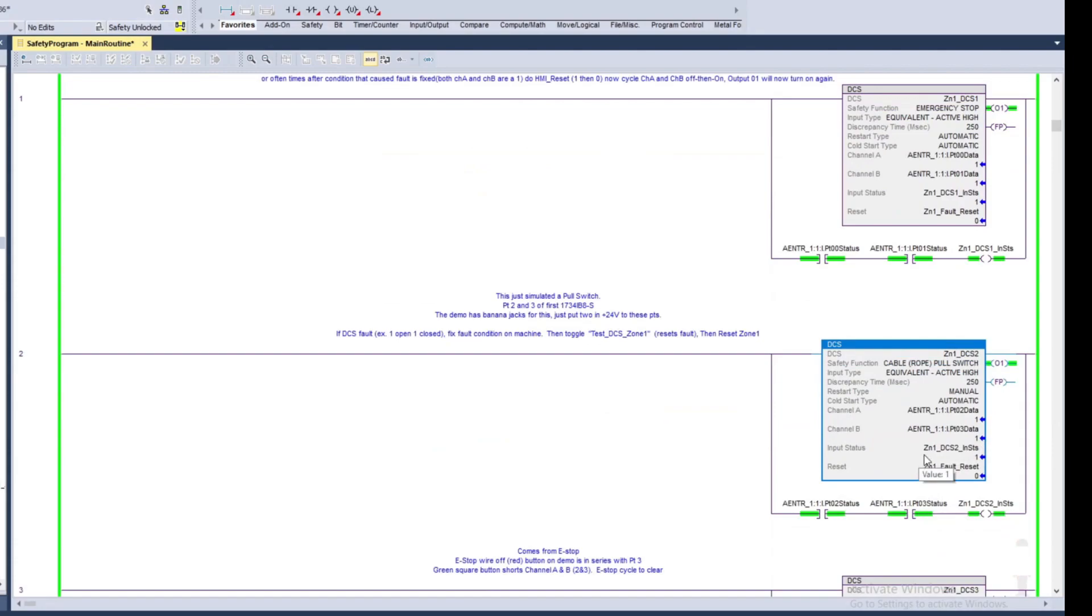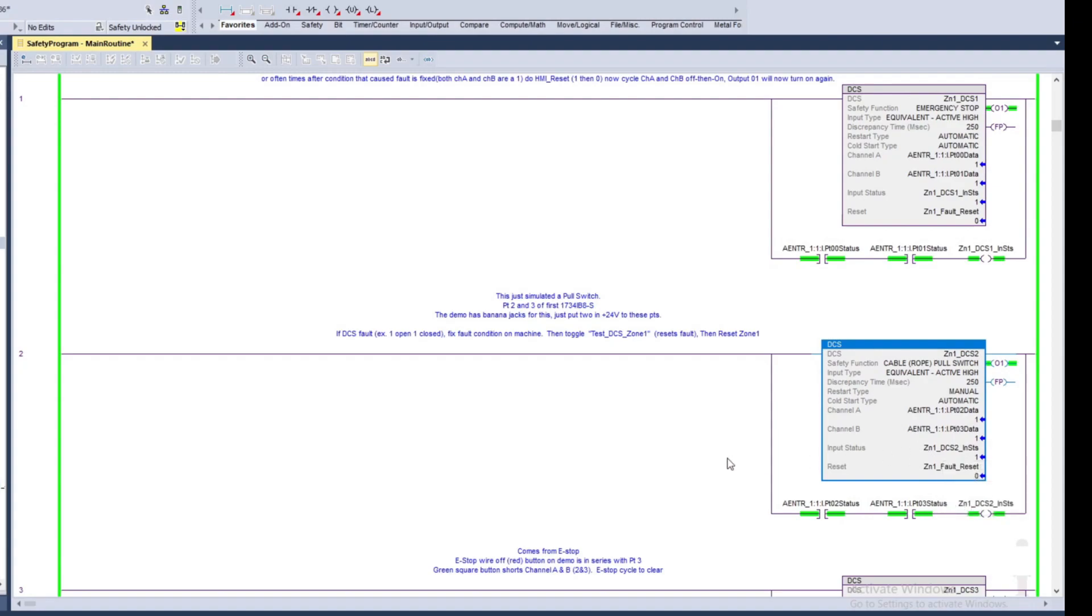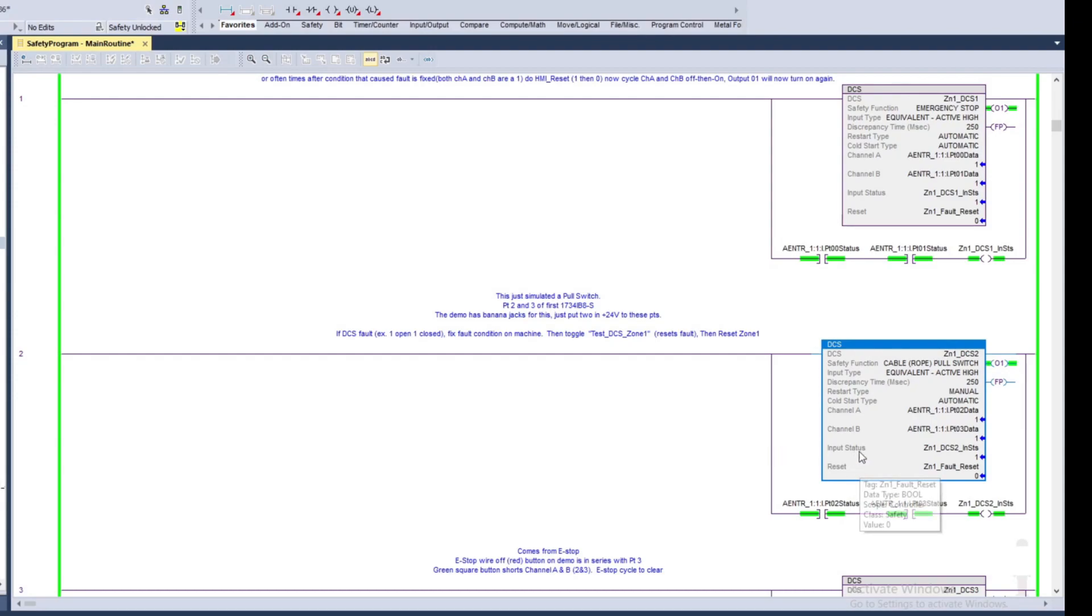And then the input status, we'll just go ahead and set this up. I can set this up a number of ways as well. I could have it check the whole module status. Sometimes you'll see it where it'll say, you know, Zone 1 underscore DCS 2 dot combined input status, in which case if any of the inputs on that module are bad it would fault the DCS instruction.